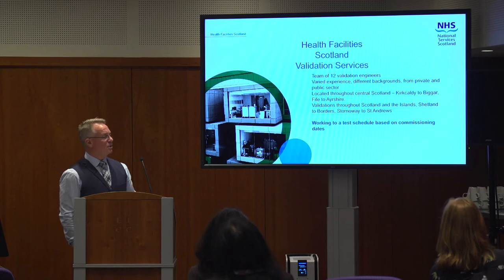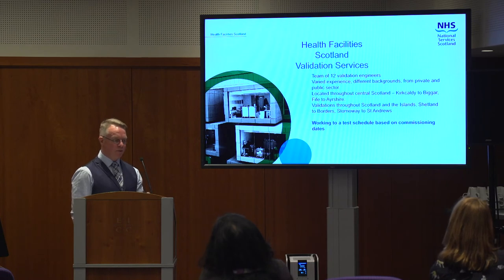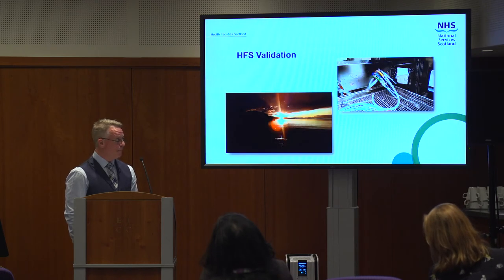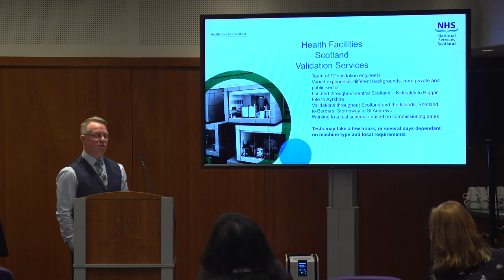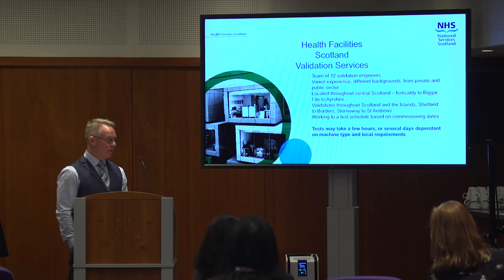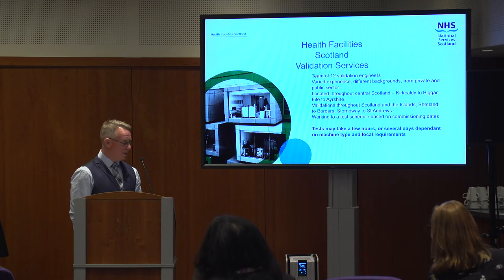That test schedule on an annual basis is really based on when the machines went into service. The local guys look after things on a weekly and quarterly basis, and then we come in on an annual basis to do the more comprehensive tests based on that commissioning date. If you're working on an endoscope reprocessor you could be there for several days; if you're doing a small benchtop sterilizer that might just be a few hours on site. Travel time can vary greatly as well.